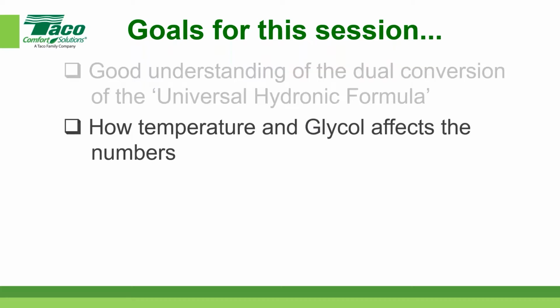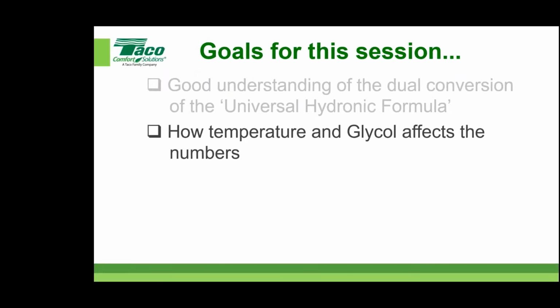There are certain things within the liquid that affect these numbers, and we'll show you how that transpires. You folks use glycol, I'm sure of it, and you'll see how the glycol affects the number you're using. When we're moving fluid through pipes, we call the speed of that a velocity, and that impacts the pipe sizes. Depending on what we want to stay above or below, you'll see how that all comes together as well. And a real short bit on the difference between a pressure drop estimate and an actual calculation. We'll show you the differences there. Finally, if we have enough time for this session, we'll get into Cv and how that affects pressure drop as well. So let's jump into it.